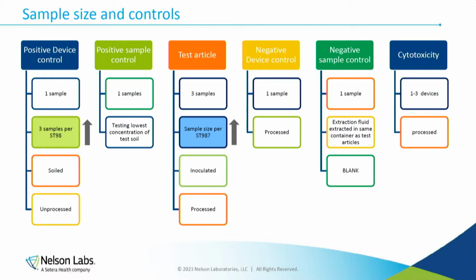Controls such as negative device controls and positive sample controls never existed in TIR30. Now we have those controls in there just to make sure that the analytical tests we're using are validated and they're pulling the test soil that we're using for the devices, okay?